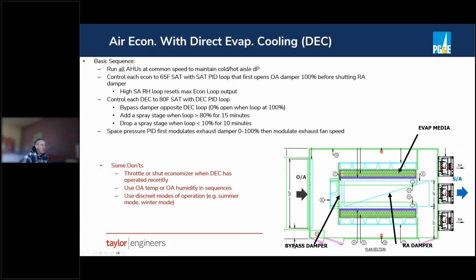So that's the economizer. This air handler here is showing the outside air damper here, and the return damper coming from above. And that's how we would modulate those economizer dampers. And then the direct evap will have a separate supply air temperature set point. So we might be controlling the economizer to 65, and we might not turn on the direct evap until our supply air gets to 80. So there could be a period of many hours during the day where the outside air temperatures stay at 67, 70 degrees, and we'll just be supplying 100% outside air. But when it gets all the way up to 80, then we'll turn on our direct evap, and we'll have a PID loop that's going to modulate.